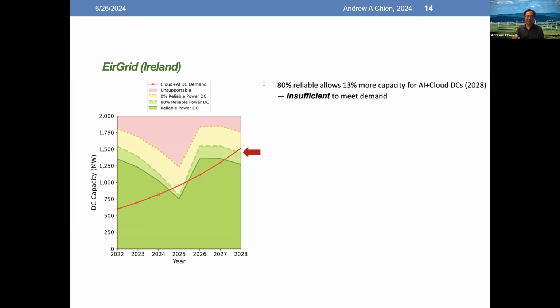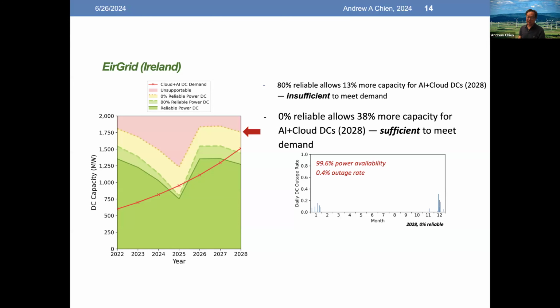But how bad is it for the data centers? Well, if they accept that guarantee, it turns out that when you simulate for the year, they get 99.6% power availability and a 0.4% outage rate. So the answer is it's actually pretty good, and this may actually be a higher availability rate than they've experienced in certain other power grids in recent times. I won't pick on any particular power grids, and probably okay because they have reliability provisioning inside of the data center as well.